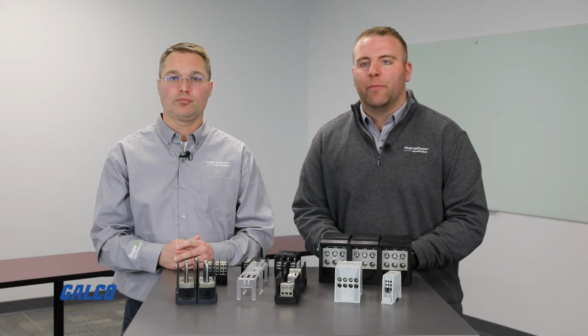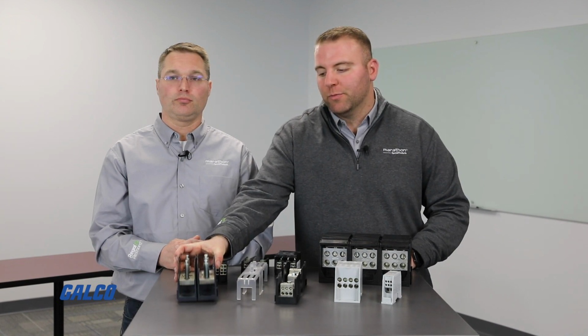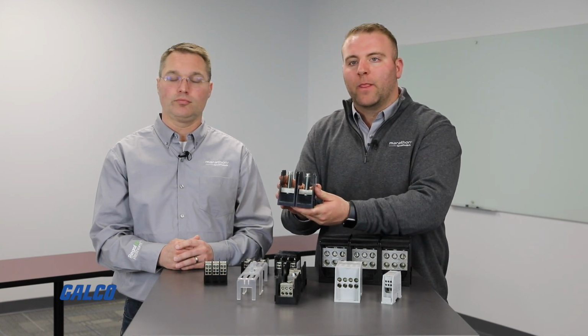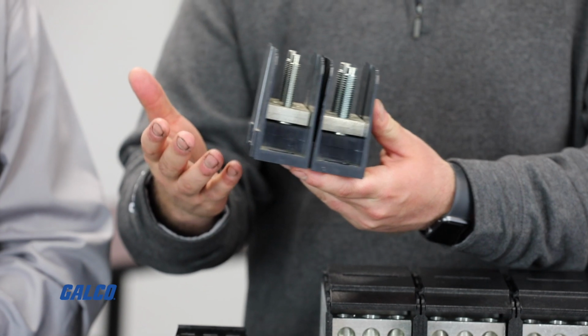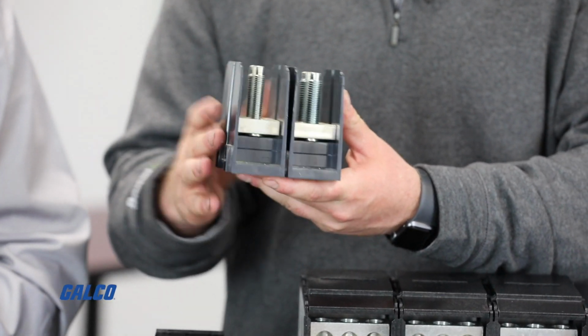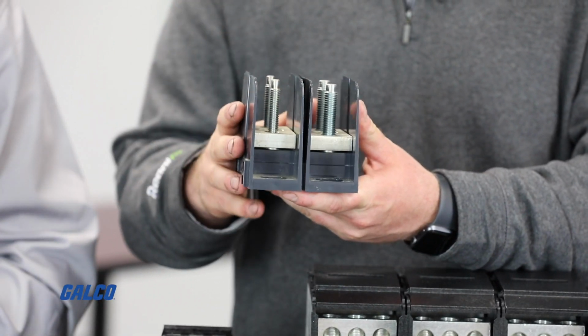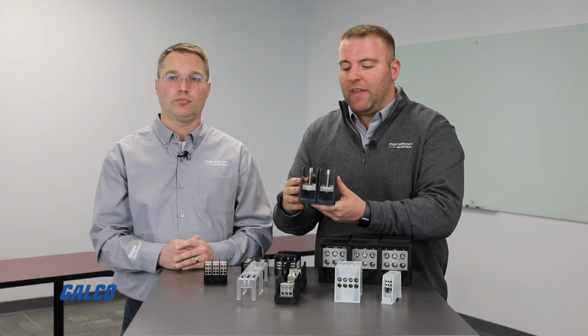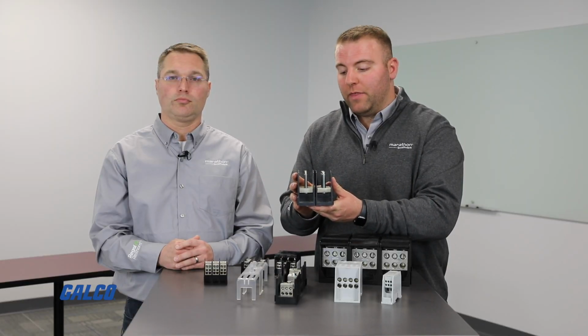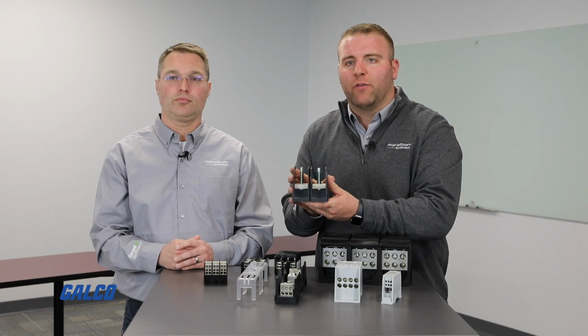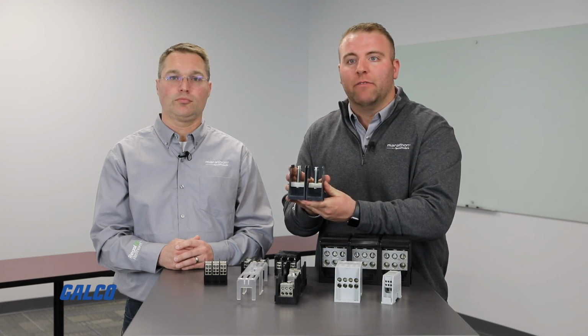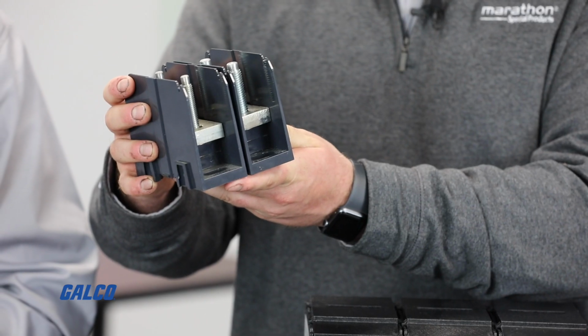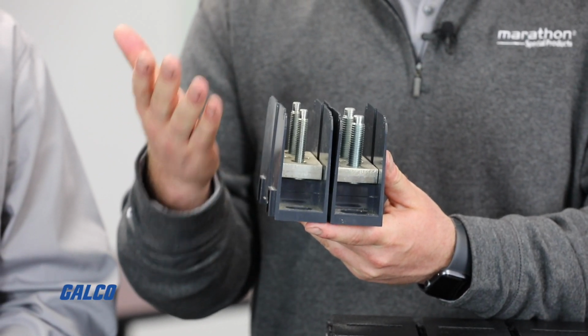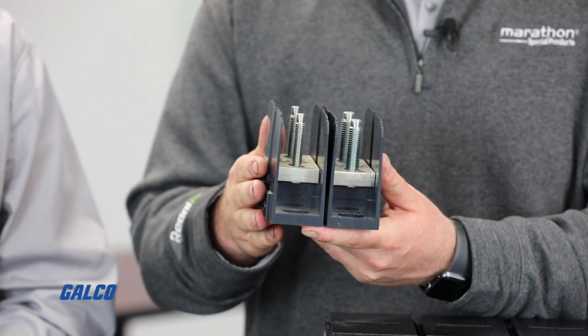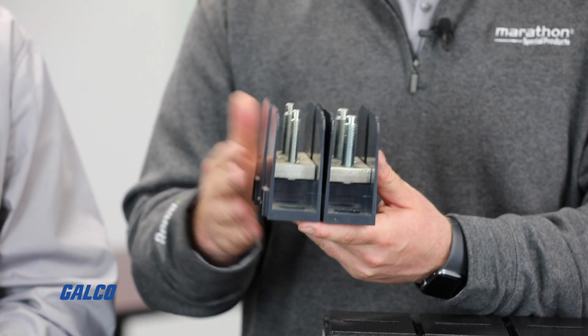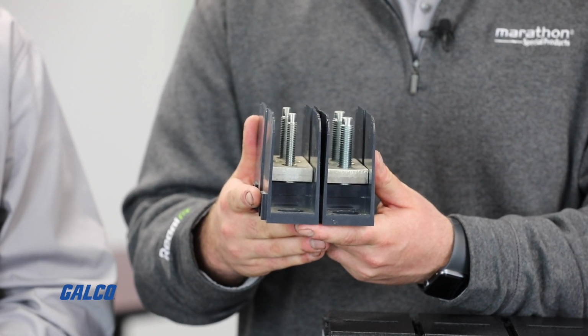Additionally, I'd like to talk about our studded power distribution blocks. These are very competitive because, simply with a crimp lug on line and load, the termination makes it very competitive, along with the fact that these are rated for very high amperages and very high voltages. For example, the HVPB114, our high voltage power block, is rated for up to 1500 volts and well over 1000 amps.